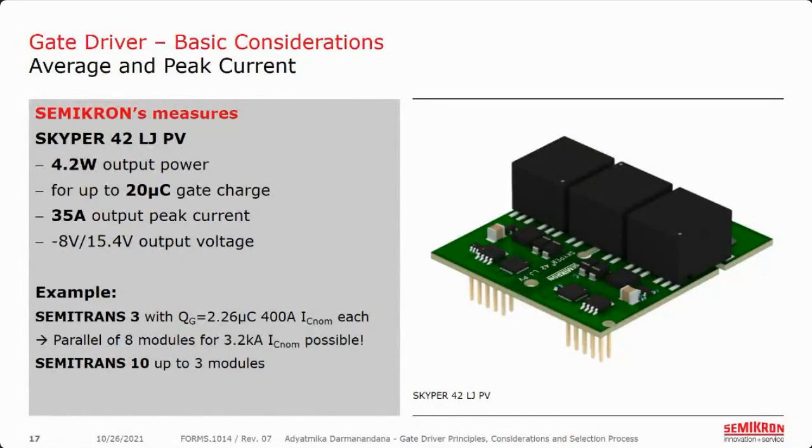It is also to be noted that higher gate charge may require a boost capacitor for the driver to secure a stable performance. Using the previous example, it means up to 8 modules of Semitrans 3 can be operated in parallel using the Skyper 42 LJPV, or 3 modules in the case of Semitrans 10. But of course, you need to check it in the end application.